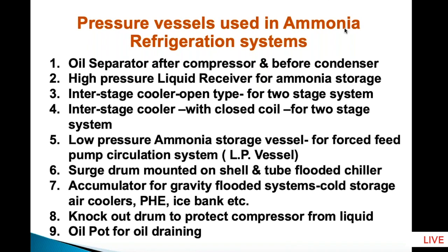The next is the surge drum and the low pressure ammonia LP vessel. This LP vessel is used only in case of force feed ammonia circulation systems and not in gravity flooded systems. The next item is the surge drum mounted on a shell and tube flooded chiller. The next item is the accumulator for gravity flooded systems, as against the LP vessel, which is item number 5. So this is used in gravity flooded systems. The next item is the knockout drum to protect the compressor from liquid. And the last vessel in a system is an oil pot for oil draining.